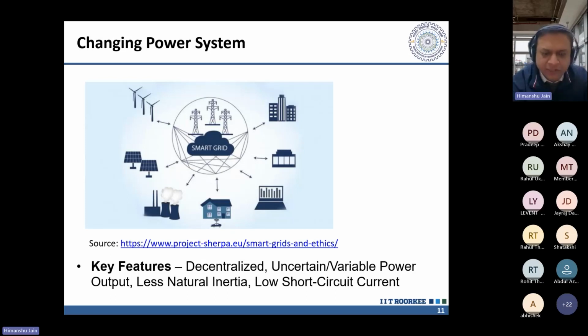There is less natural inertia. Your solar plants and new wind power plants don't provide natural inertia to the grid like synchronous machines used to and currently do. And finally, your inverters don't provide as much current as a synchronous machine would under fault conditions, so you have low short circuit current.